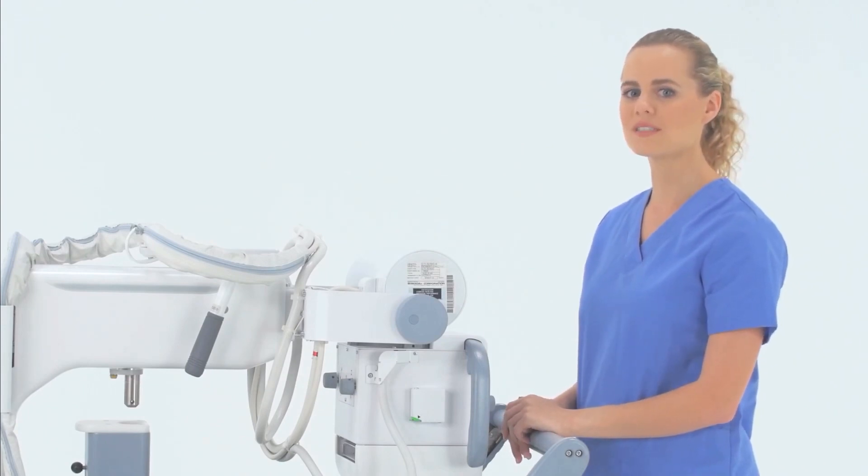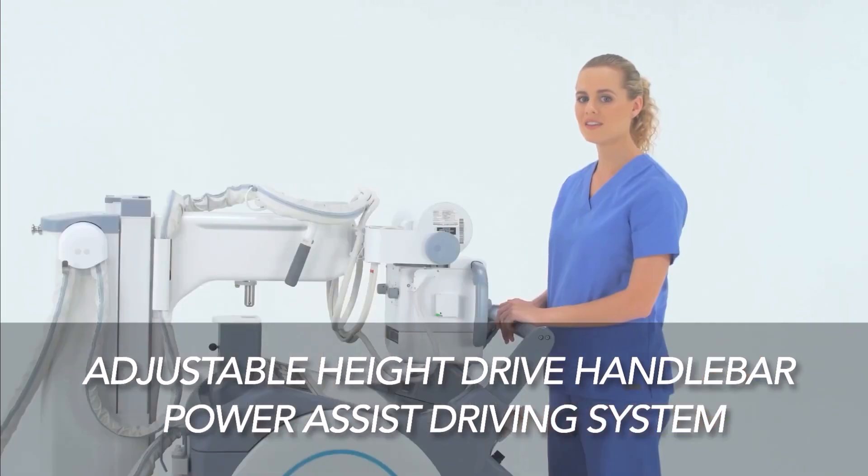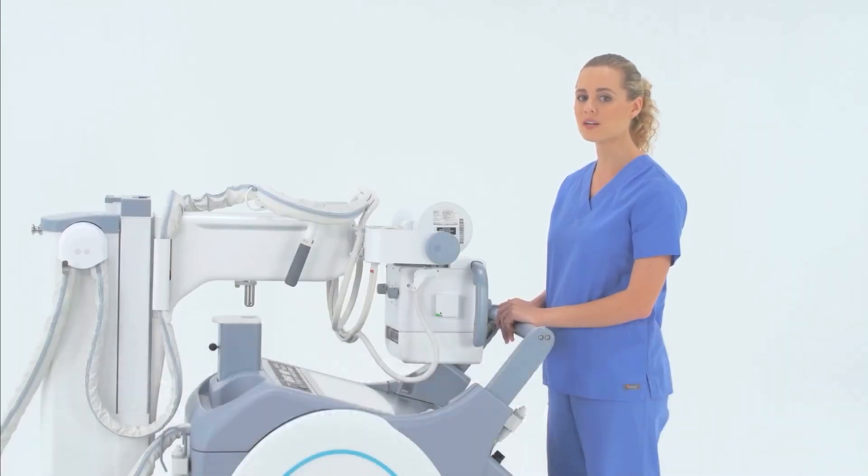The MX8 mobile system is easier than ever to maneuver now too, thanks to the new adjustable height drive handlebar and power assist driving system. The drive handlebar can now be extended or collapsed by pressing both side buttons simultaneously to better accommodate technologists.